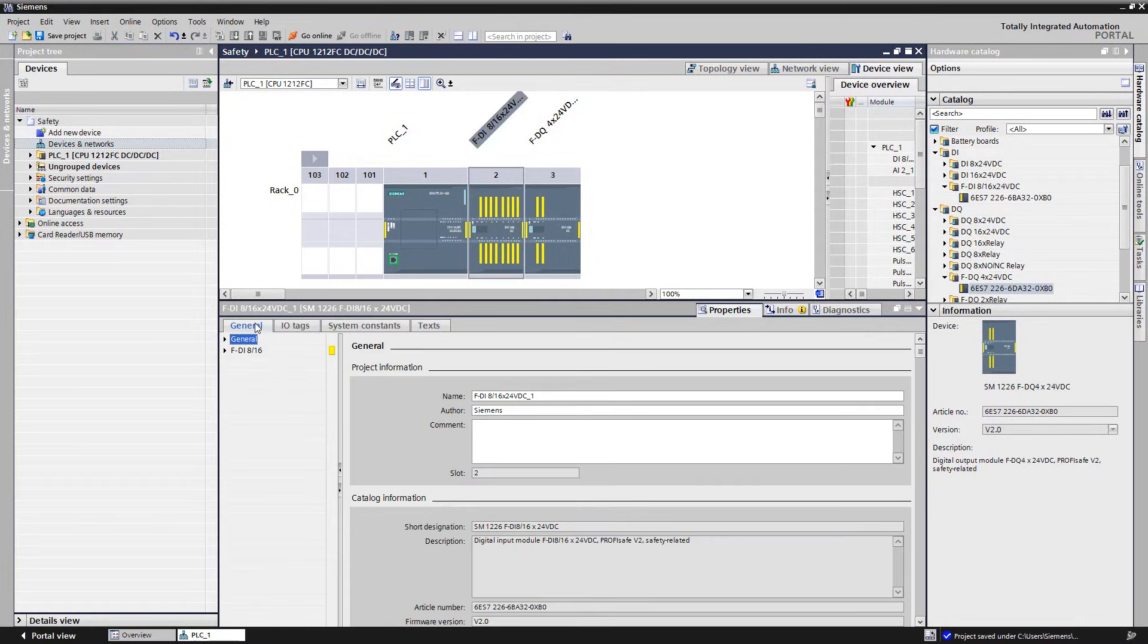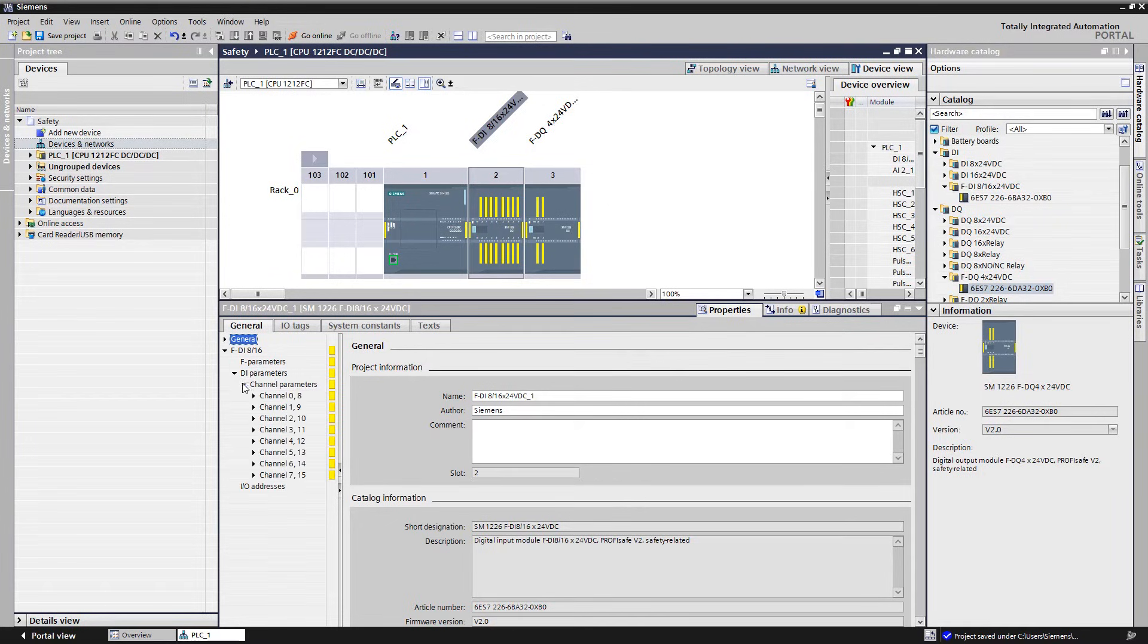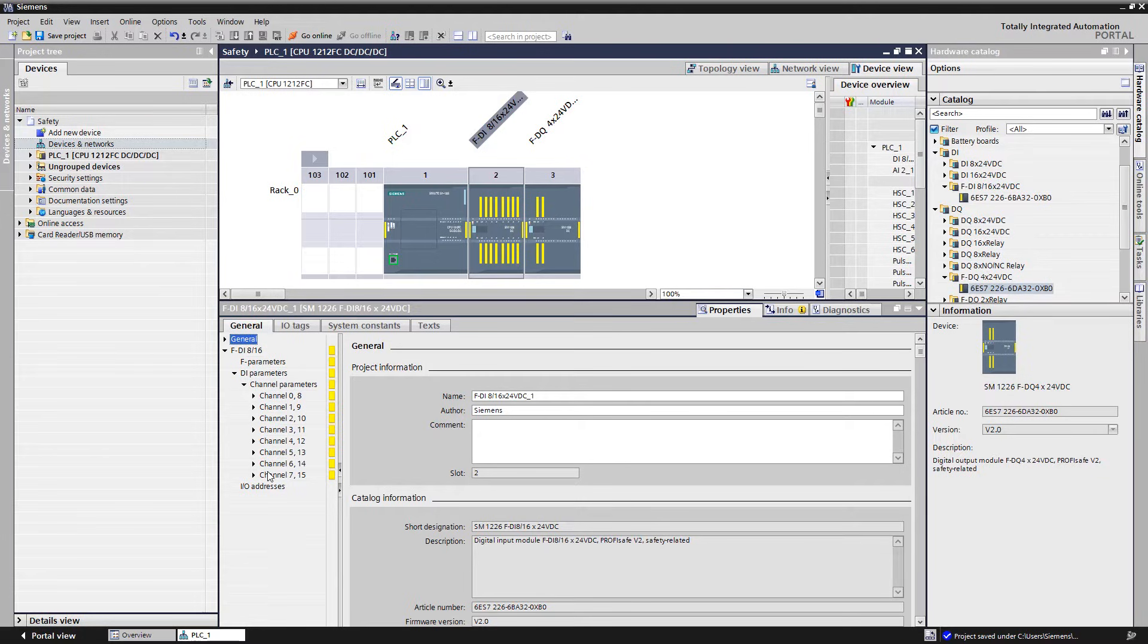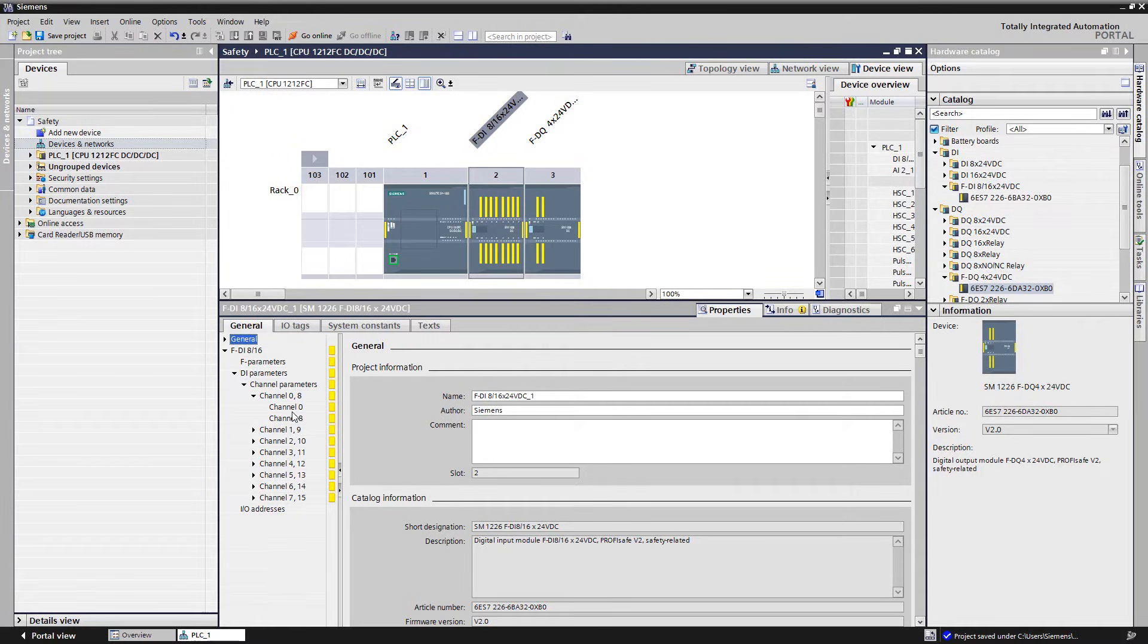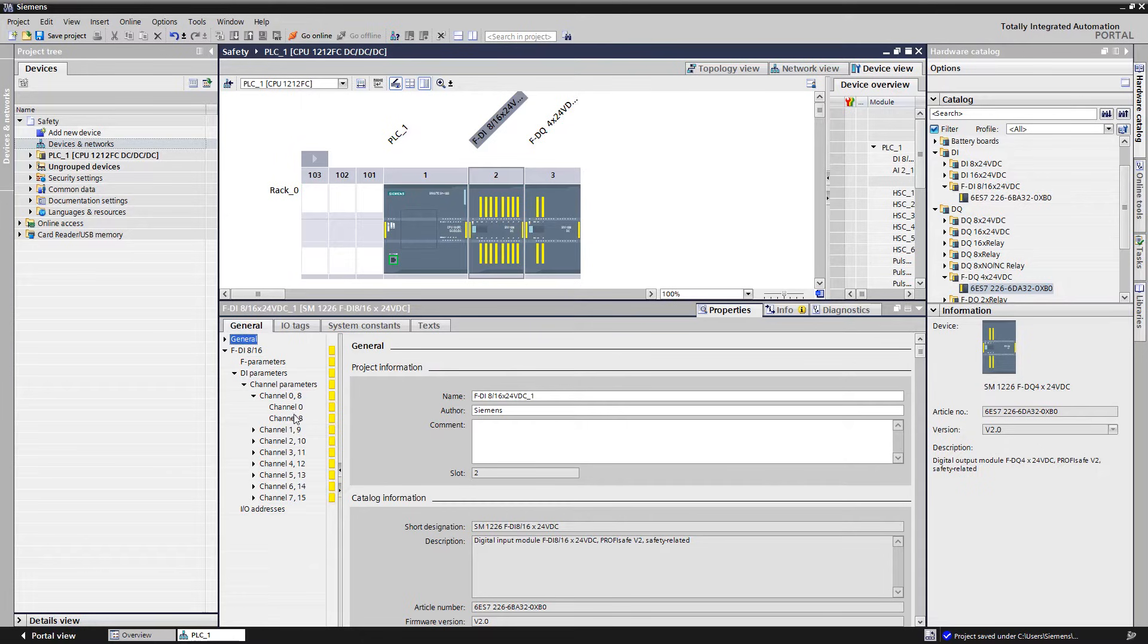The respective parameters must be set in the properties of the F-DI module. The physical input channels are always arranged in pairs in the input mask, but with a two channel evaluation they are later considered as only one signal in the safety program. The term 1 out of 2 therefore means that the module combines two input channels to one safe signal.